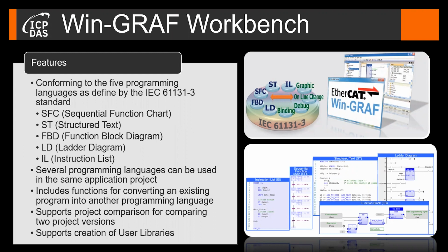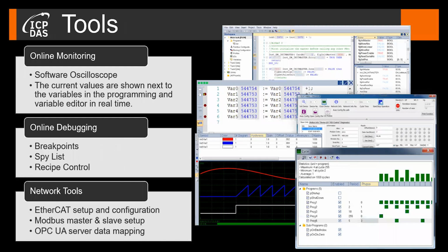The five PLC programming languages, such as structured text, function block diagram, ladder, etc., are all compliant with the IEC 61131 standard. The Win-GRAF Workbench development environment comes with plenty of tools for editing, configuring, monitoring, and debugging the PLC application program. Included are network configuration tools for setting up the EtherCAT master, the Modbus server and slaves, and for integrating the OPC UA server.